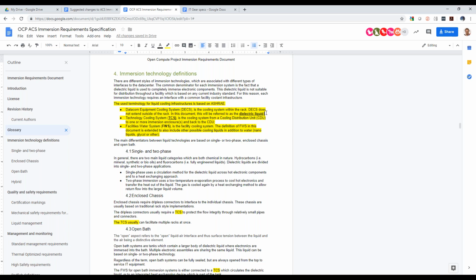So is the dielectric directly pumped within the server chassis system? Let's take for example the interface and break between the dielectric pumped CDU and the tank. I understand. Let's take a GRC solution, for example. You have one CDU that circulates oil across 4 tanks. And the oil is a dielectric liquid. It's being circulated through 4 separate tanks. The liquid leaves the tank, is transported by the CDU. Yes. And the CDU pumps it to a heat exchanger on the cooling tower. So I would call that a TCS.